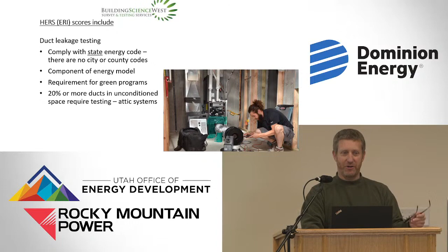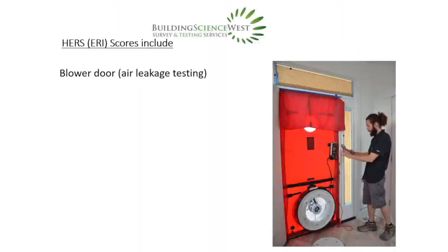Do you recall how many CFM a duct blaster will move? A lot. Couple 500. I've never seen 500, but yeah, this will move 6,000, I think. 6,000 CFM. It's much bigger. It needs to be, because the home is tested at 50 pascals, the ducts at 25 pascals, double the pressure, and of course the space is a lot larger. And again, you can see that we've got an aluminum frame. You can't see that it's aluminum, but it is, and then an airtight fabric door that the fan fits into, that allows us to depressurize the home.